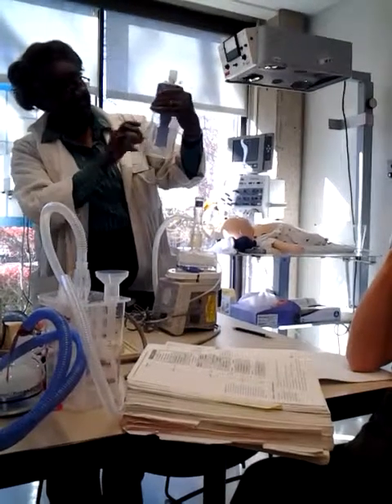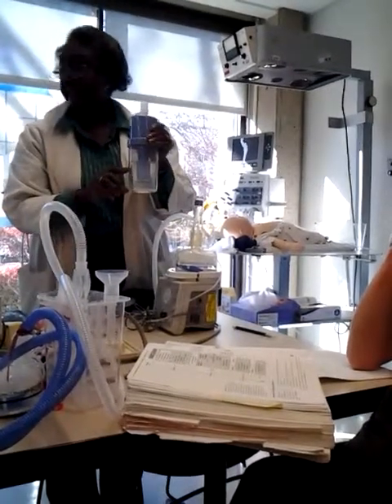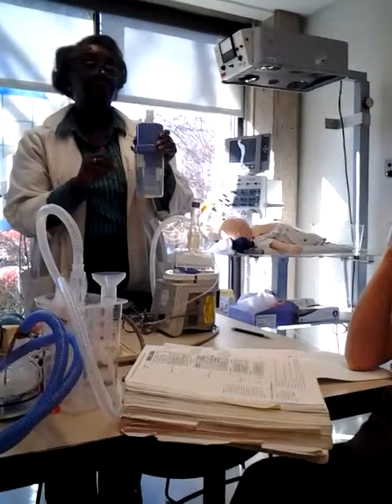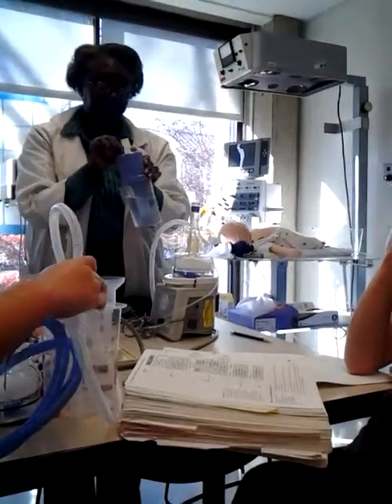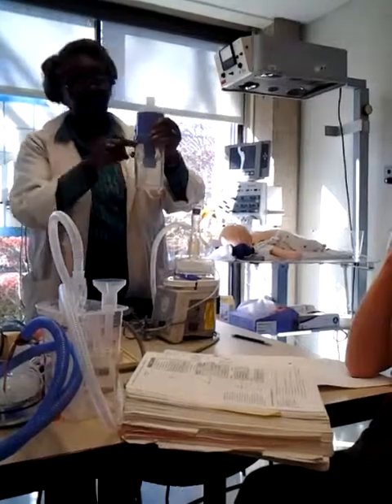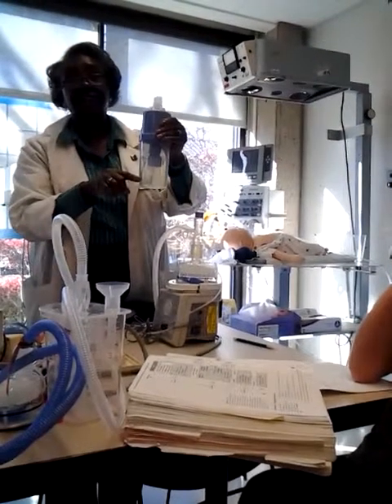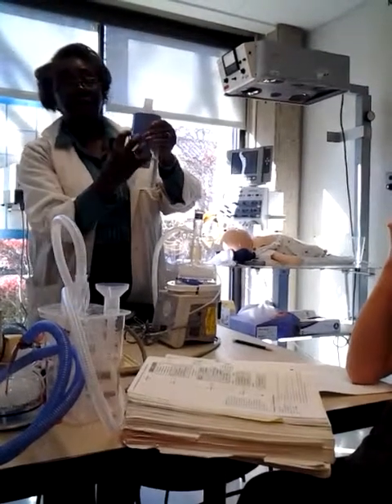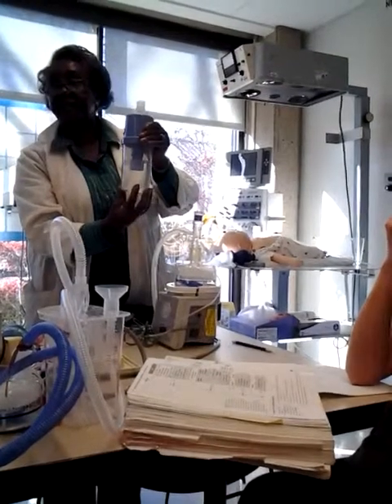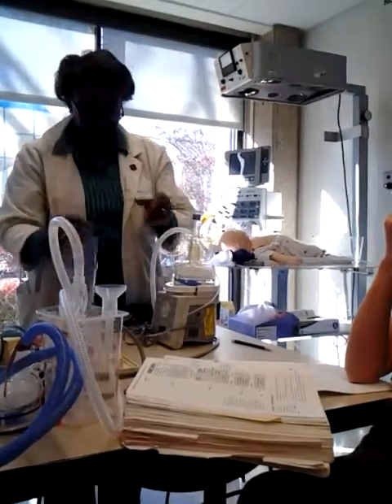If this was all the way full to the fill line, it's going to generate 7 centimeters of water pressure, CPAP. If I dial this down to 4, you notice it comes up in the water a little bit, so it's going to generate less pressure. It's underwater because it's going under the water, and that's creating that back pressure against the baby's airway.